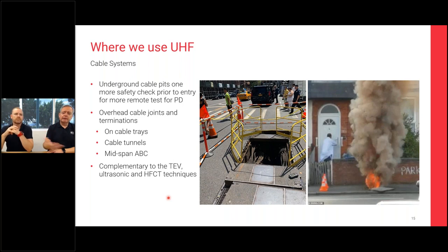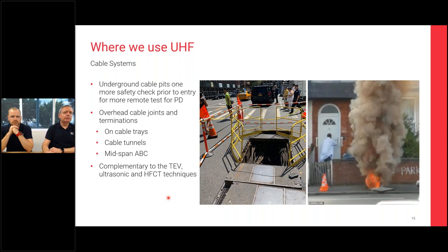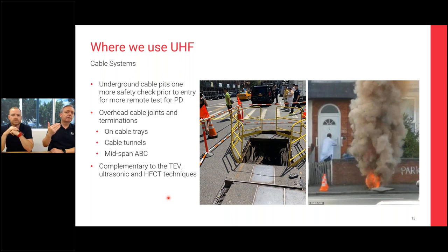For directly buried cables, HFCT techniques are used, but in many situations — cables on cable trays, joints overhead, cable tunnels, underground areas with cables on gantries, or mid-span ABC joints — you can't physically get up there to do a TEV test, so we measure everything remotely using UHF. It's a complementary technique to TEV, ultrasonic, and HFCT for cable systems.